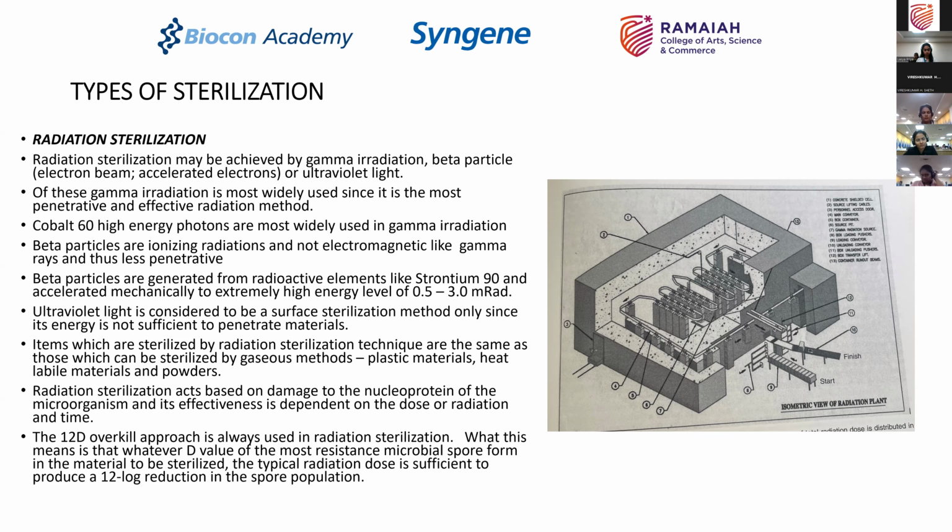We're not going to talk too much about ultraviolet light, because from a regulatory perspective it is not considered a sterilization process any longer. Gamma radiation, yes. Electron beam radiation, yes. But ultraviolet, no. Of the two, gamma irradiation is most widely used.